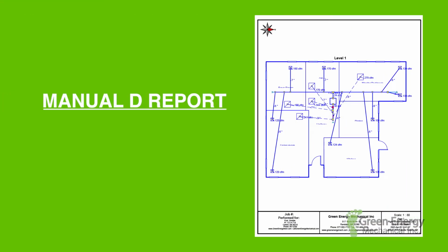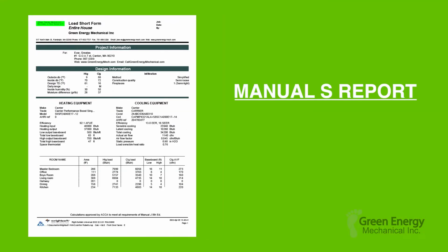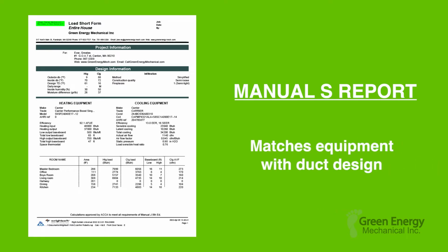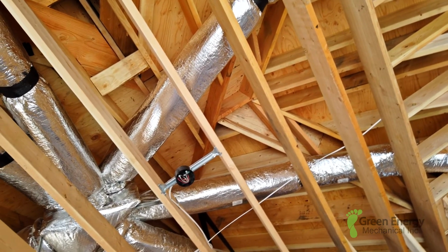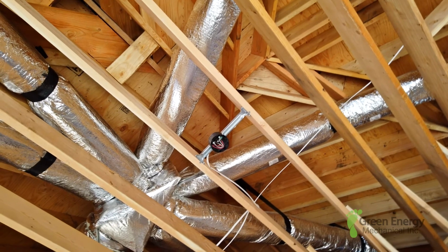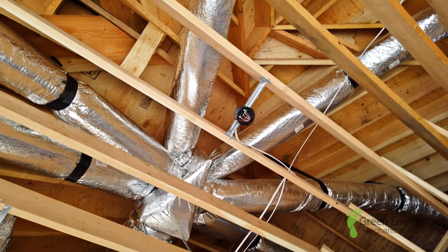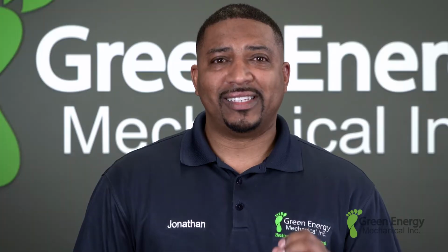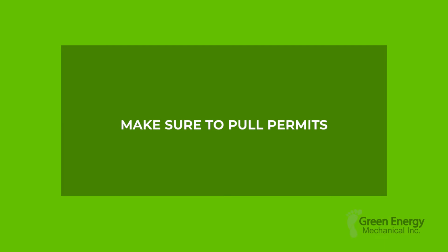If you're having new ductwork installed, the manual J should also come with a manual D report. This is a duct design based on the manual J report. Another form needed is a manual S report, which makes sure the equipment spec'd out will match the duct design and the heating load needed for your home. Proper duct design is crucial to delivering warm air to all the spaces evenly and efficiently. Without one, your contractor's winging it. Insist on these reports before you receive a proposal from your contractor. And even if you're installing ductless split systems, you still need to make sure that they're sized correctly according to a manual J report.